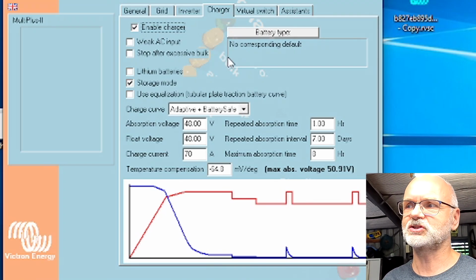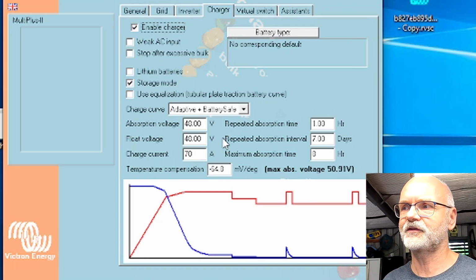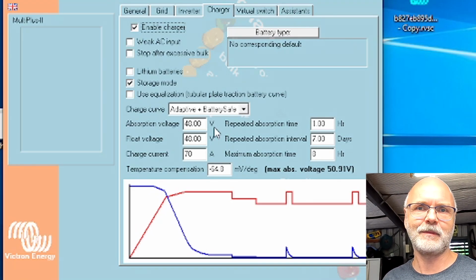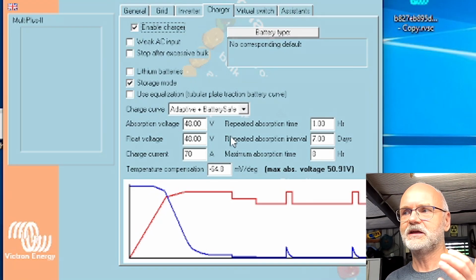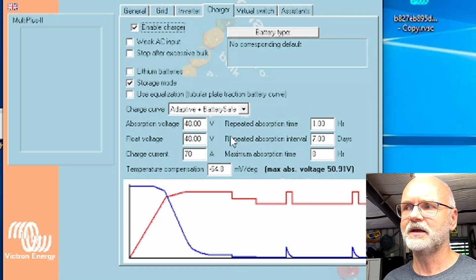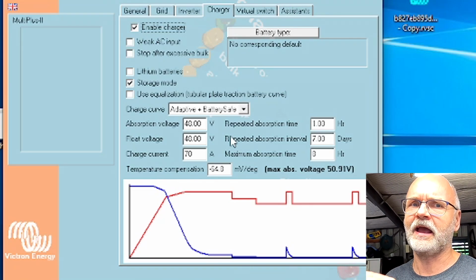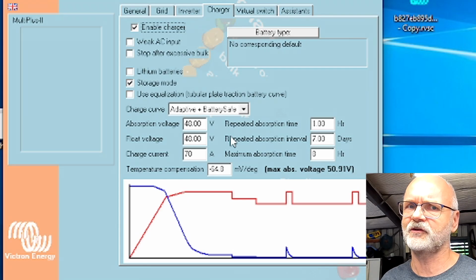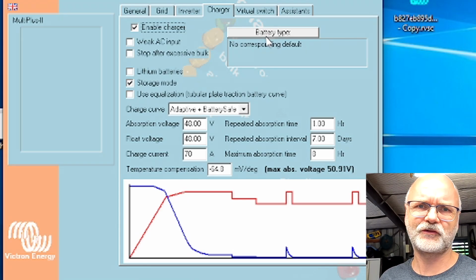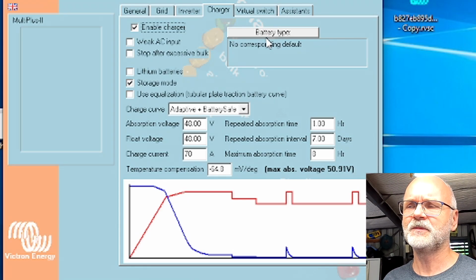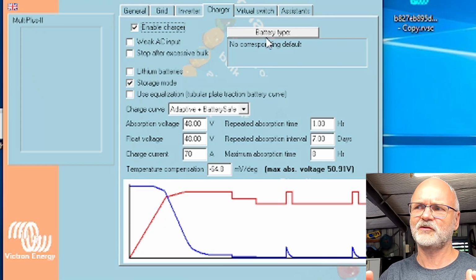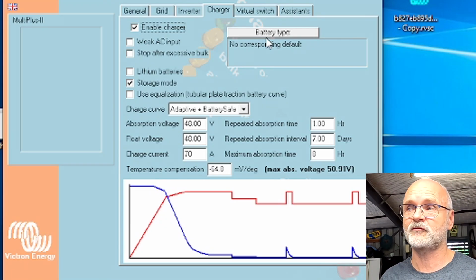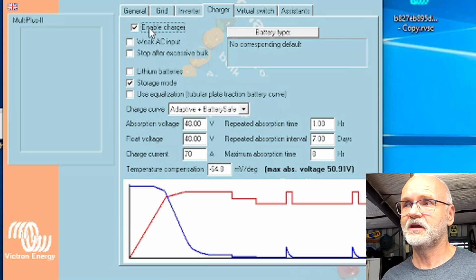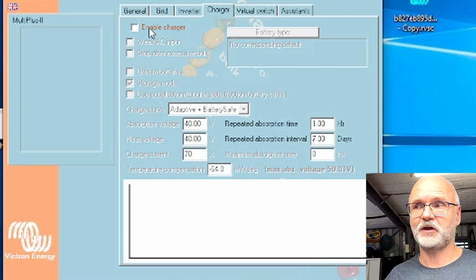But this is the location where you can set all your absorption, your float voltage, your charge currents. This is basically the same as in the solar charge controllers. You can set everything up in here. And I think these settings here actually override the settings in your solar charge controllers. You can also load different battery types in here. So it's a very similar setup to what you have in the solar charge controllers from Victron. But in this case, we turn off the charger altogether.